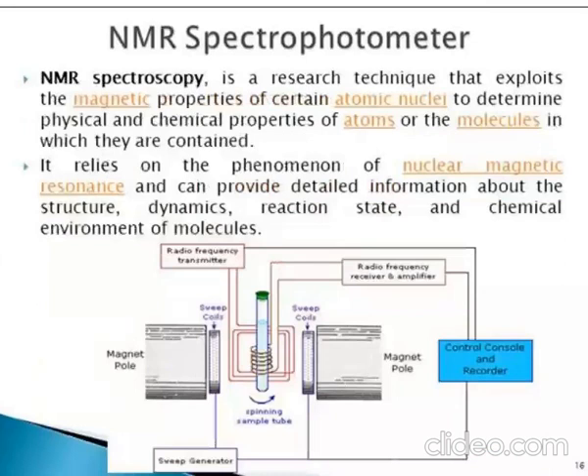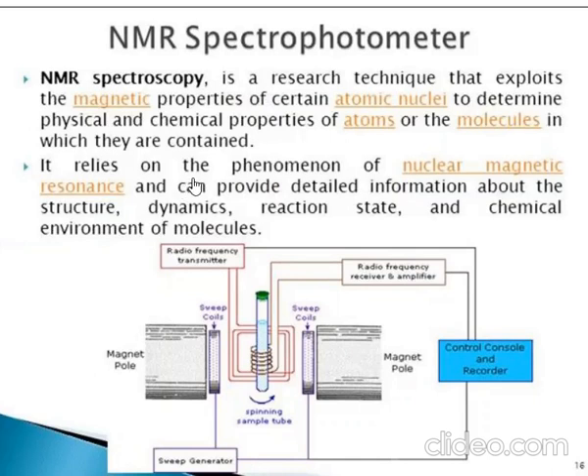NMR spectroscopy is a research technique that exploits the magnetic properties of certain atomic nuclei to determine the physical and chemical properties of the atoms or molecules in which they are contained. It relies on the phenomenon of nuclear magnetic resonance and can provide detailed information about the structure, dynamics, reaction state, and chemical environment of molecules. The instrument includes a magnet, transmitter, radio frequency amplifier, and recorder.